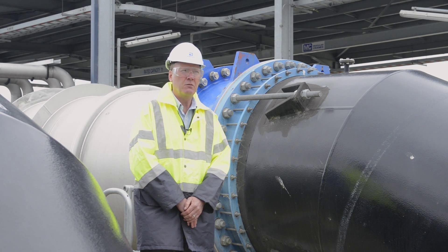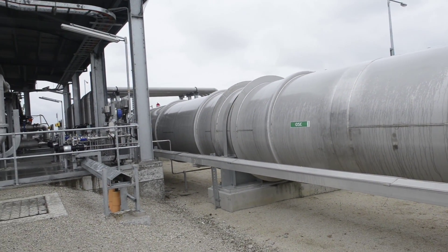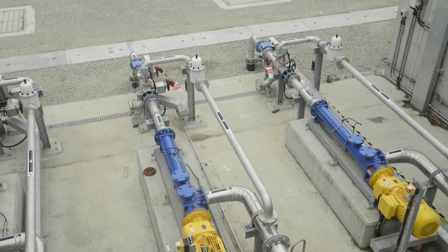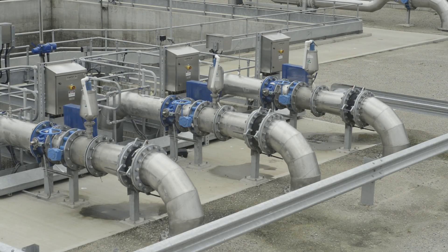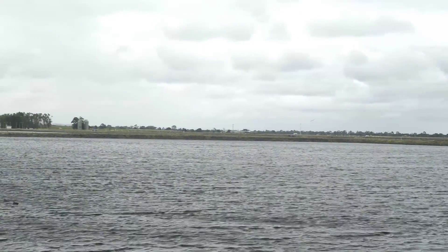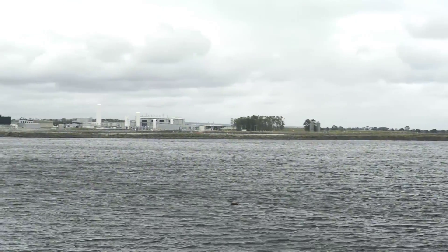It also provided opportunities for increased recycling of the treated effluent from the treatment plant. We built upon the work that Melbourne Water did to construct a trial scale facility, and through that we selected a process train of ozonation, media filtration, ultraviolet irradiation, and chlorination that has provided tremendous improvements to the quality of the discharge into the environment and a fit-for-purpose recycled water quality that can be used by the community.